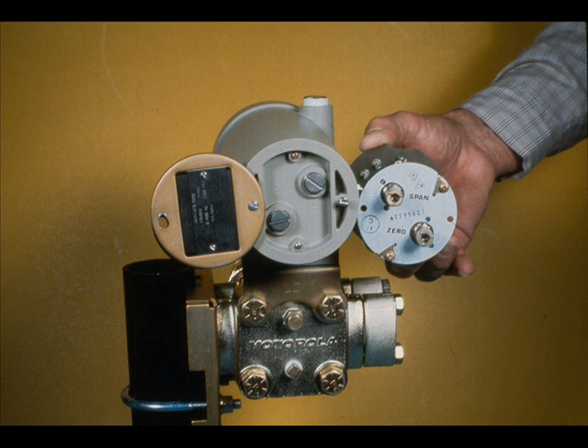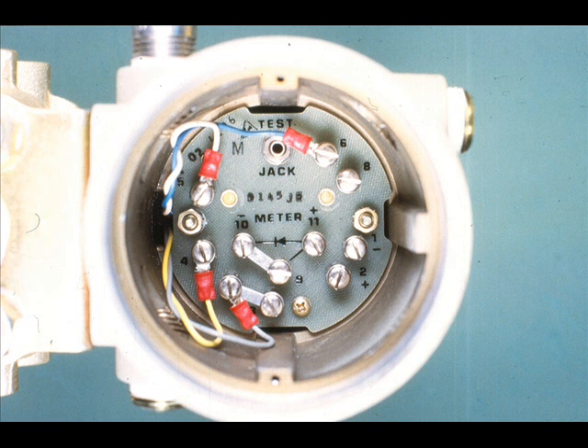These are the zero and span adjustments. Here, the 24 volt DC positive and negative terminals are shown. The four wires to the left are from the measuring cell. The test jack is for measuring the transmitter output. A local or remote indicator may be connected across meter terminals 10 and 11.